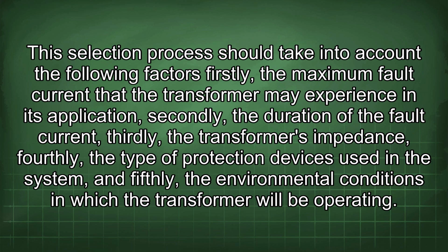Firstly, the maximum fault current that the transformer may experience in its application. Secondly, the duration of the fault current. Thirdly, the transformer's impedance. Fourthly, the type of protection devices used in the system. And fifthly, the environmental conditions in which the transformer will be operating.